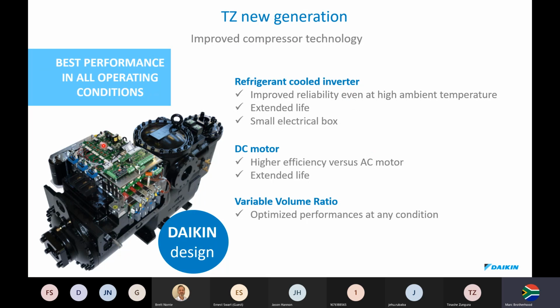Well, first of all, the electronics is built on top of the compressor body. What's the advantage of this? Well, refrigerant cooled inverter. So we take subcooled liquid from the condenser. We don't physically use evaporator temperatures because that would create sweating and it would blow the electronics. But these electronics run at about 85 to 90 degrees. Subcooled liquid from your condenser is probably around 45 degrees.